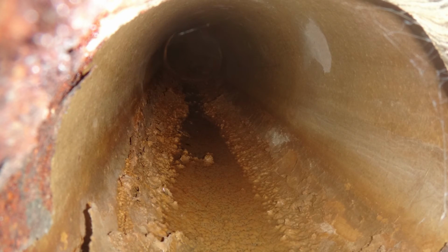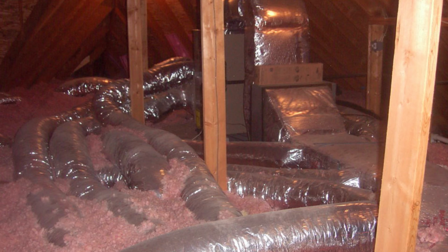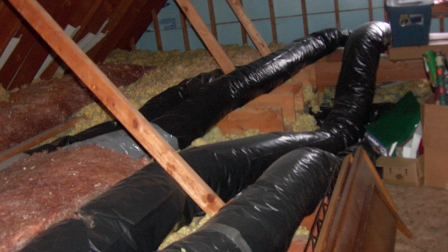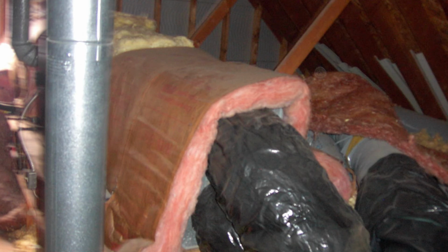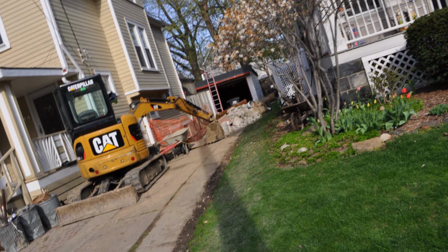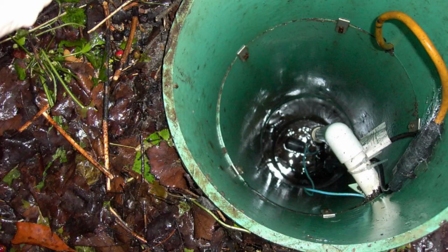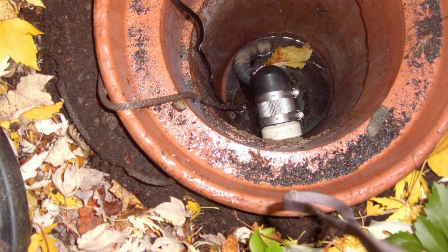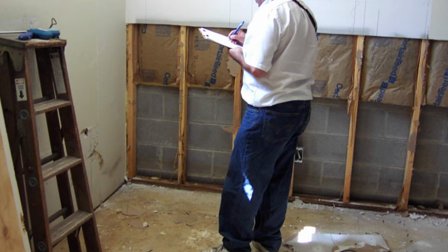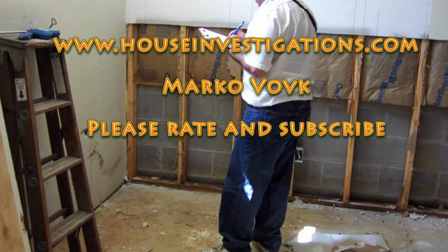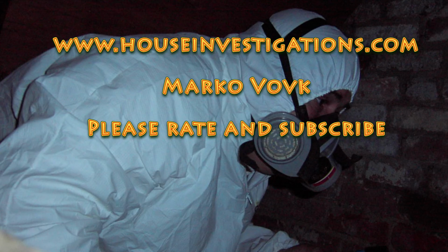Repairing this home would not be easy. One repair method that may be successful would be filling the under-slab ductwork with concrete, changing the furnace from a downflow to an upflow, installing all new overhead supply ducts in all rooms, and adding several return ducts. The new ductwork should be sealed and insulated so thermal bridging, thermal bypass, and heat loss do not occur. The exterior foundation would need to be waterproofed, and adding an exterior dewatering sump pump would help lower the groundwater elevation. The home would need proper mold mitigation, entire home sanitizing, repair of all thermal bypass, repair of all thermal bridging, and finally HVAC balancing.